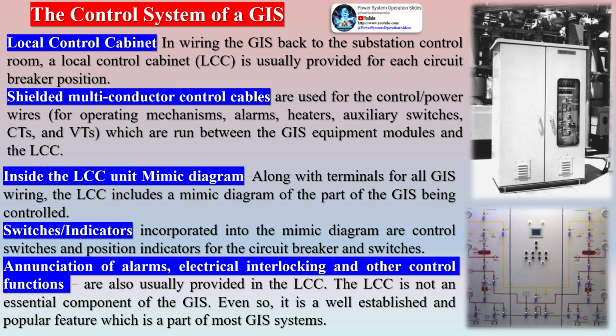Local control cabinet: in wiring the GIS back to the substation control room, a local control cabinet (LCC) is usually provided for each circuit breaker position. Shielded multi-conductor control cables are used for the control power wires for operating mechanisms, alarms, heaters, auxiliary switches, CTs, and VTs which are run between the GIS equipment modules and the LCC.